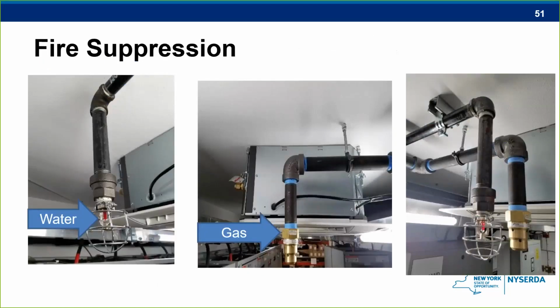So some of these containers may end up with 2 types of suppression. A clean agent, like a gas of some sort, that might act as a first-line response, and they may also be equipped with water fire suppression. Water should only be placed on these systems when there is a known fire event, if necessary, because it will ruin the batteries permanently.